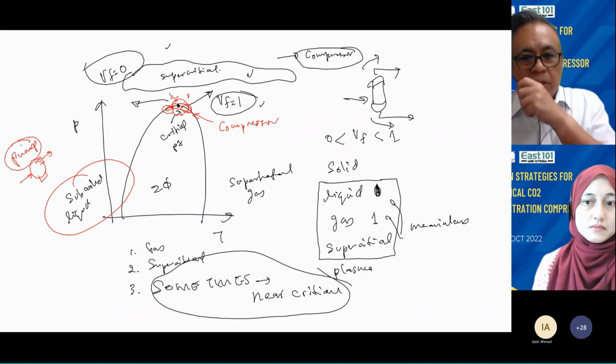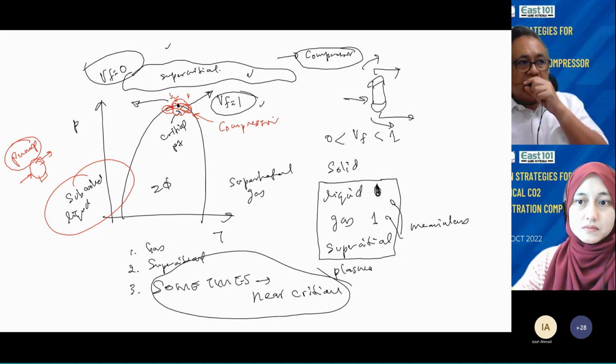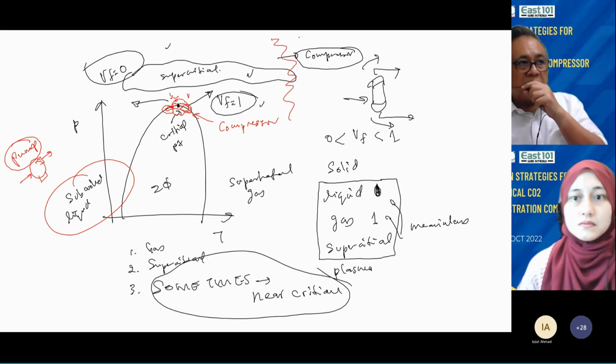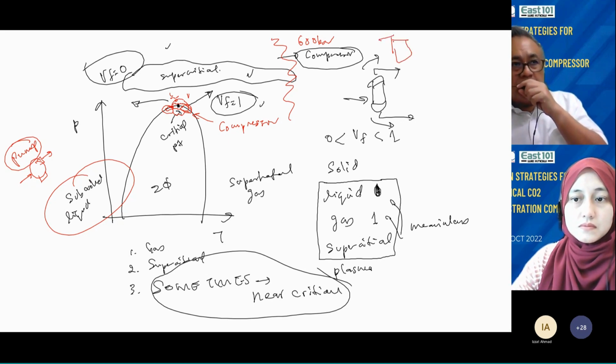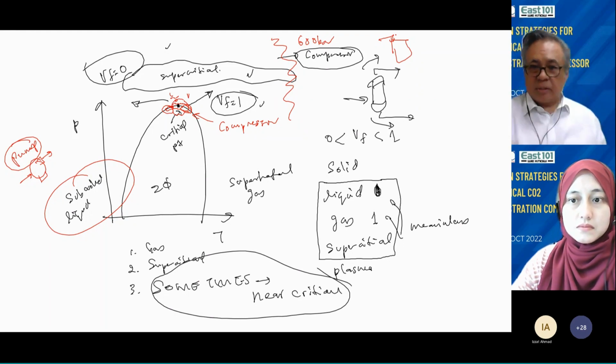So that's why we can still use a compressor in this case. Actually, in the simulation, as we start getting farther into about like 600 bar, the equipment that you buy is still called a pump. They're using these Nuovo Pignone pumps, but we are modeling them using the compressor object because the supercritical fluid is still compressible. So I hope that answers the question.